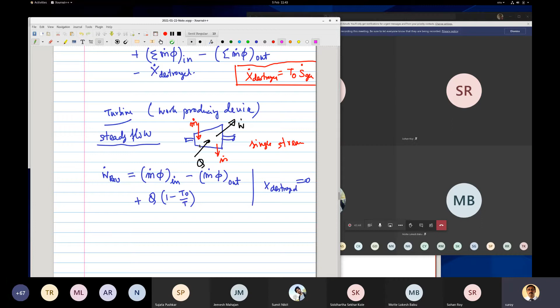When you get it from the manufacturer, I would like to know its performance. We know the condition of the steam going in, the condition of the steam going out, and if our insulation is not the best, there will be some heat transfer through the insulation. Then we can make an estimate of the reversible work, and then we can measure the actual work, and then we will know what the irreversibilities inside the turbine are because of friction and so on, whether they have designed the bearings, the channels and the blades efficiently. If the blades are not aerodynamically shaped and well designed, there will be losses. So for a well designed turbine, the work output should be much closer to the reversible work. So it is very useful.